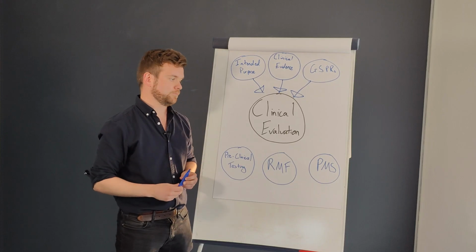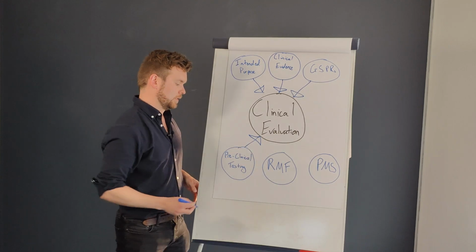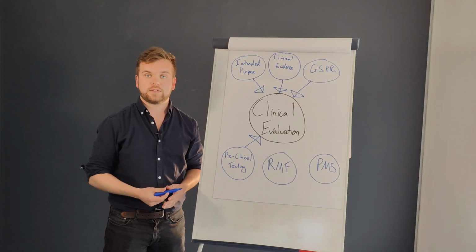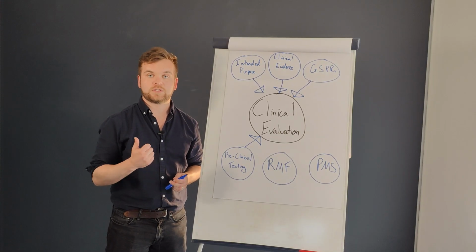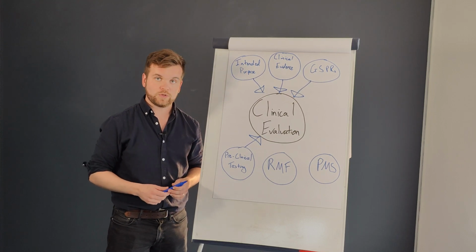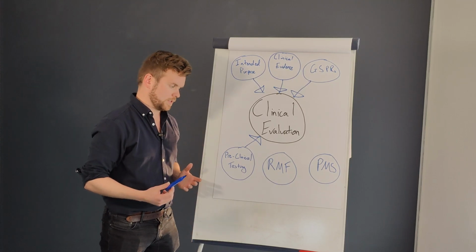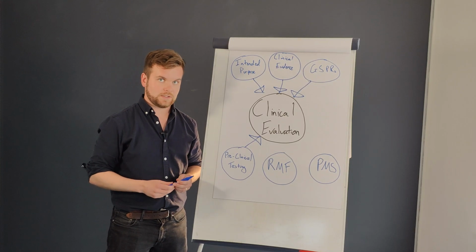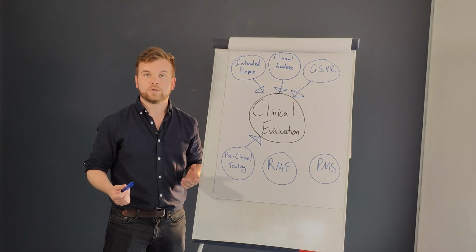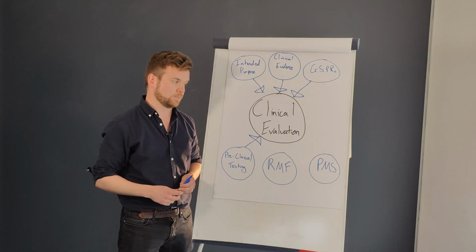Then we have preclinical testing, often referred to as benchtop testing. The clinical evaluation is a great place to outline all the preclinical testing that you've performed on your device that supports your device's performance and safety profile. When we think about preclinical tests that support performance, we're often thinking of things like verification and validation testing. When it comes to safety, the preclinical testing that you might use will be quite variable depending on your own device, but might include things like biocompatibility or electromagnetic compatibility testing, for example.